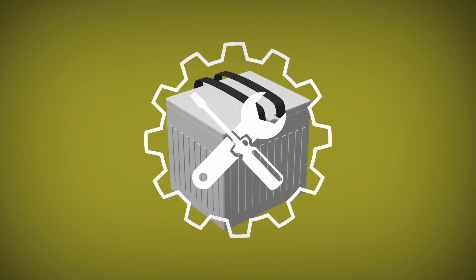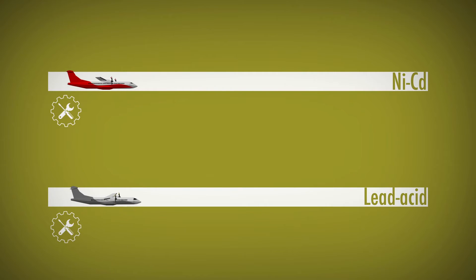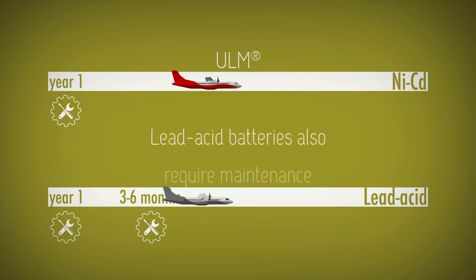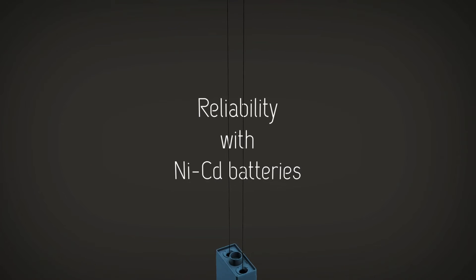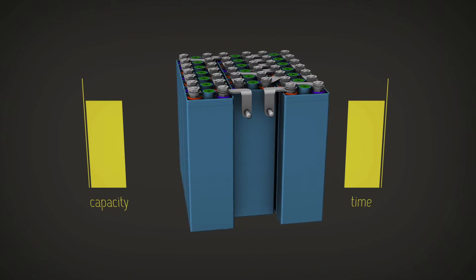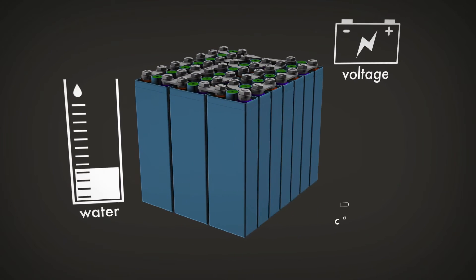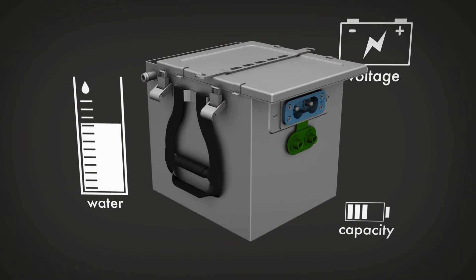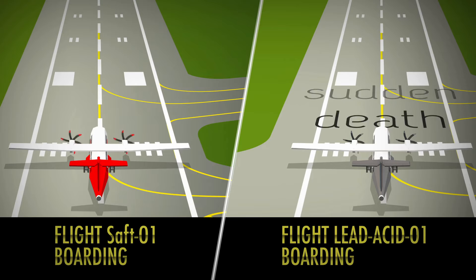There is a common misconception that lead-acid batteries are maintenance-free. False. While average battery maintenance for NICAD ULM occurs only once a year, most lead-acid batteries require one capacity check in the first year, and then every three to six months thereafter. Moreover, the decrease of capacity in a NICAD battery occurs over periods of time and is a continuous occurrence which is very predictable. Water usage, charge voltage, and capacity checks determine the battery health. On the other hand, sudden death is a common phenomenon with lead-acid batteries and is not predictable.